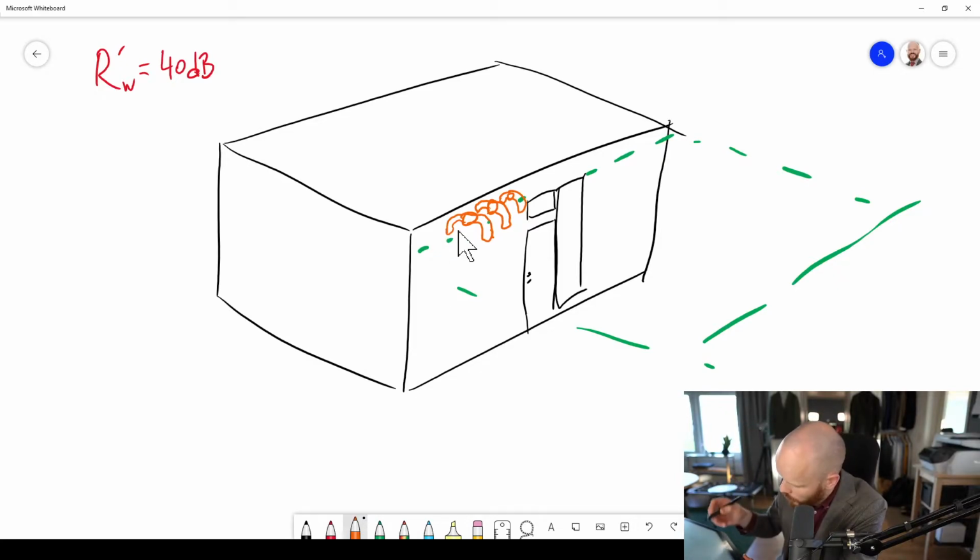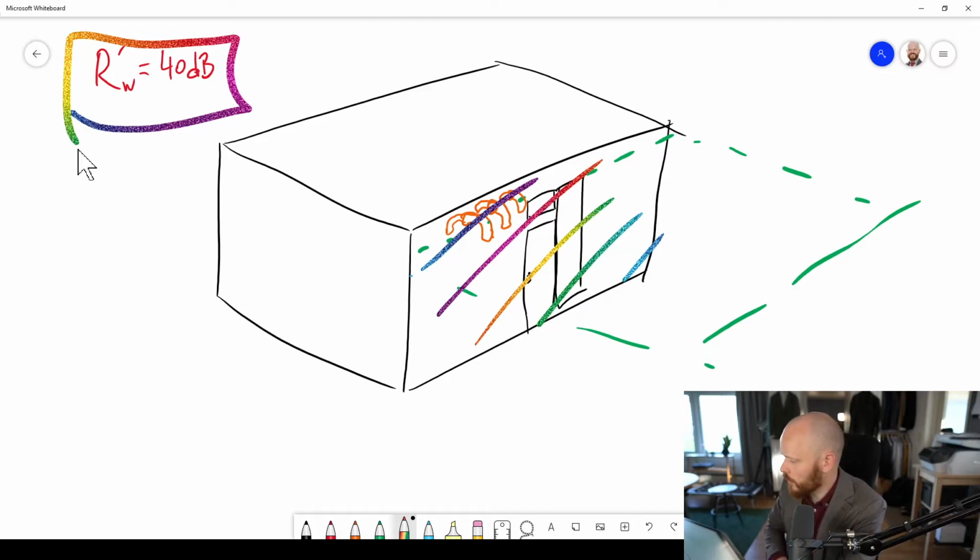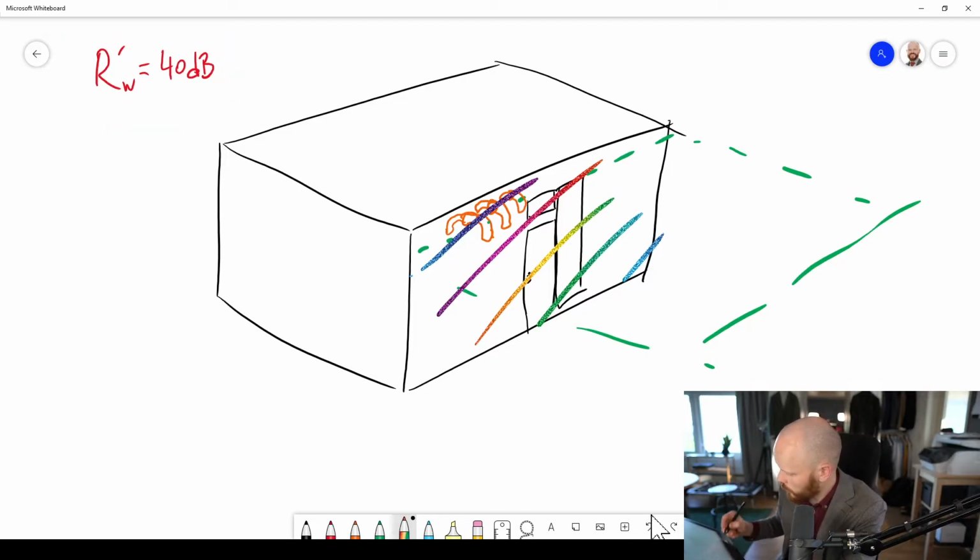for every additional transfer unit that you install in the wall, the resulting sound reduction index will go down. So even if, let's say, for this entire construction, the wall, glass, door, partition and everything, you got 40 decibels, you fulfill the requirements with the whole partition, and then you find an air transfer unit which is supposed to fulfill also 40 decibels of field. Then you should be fine.